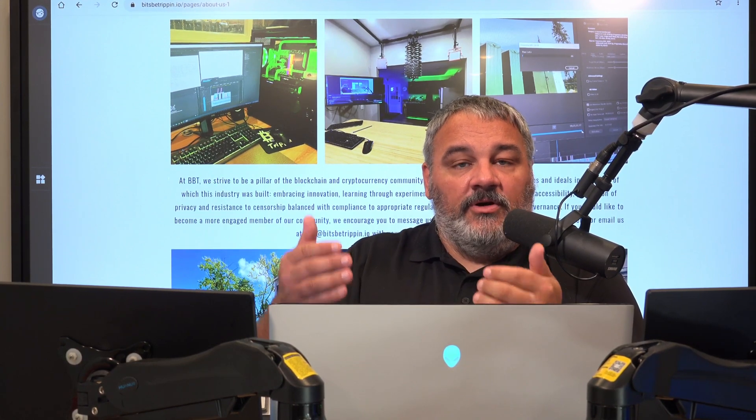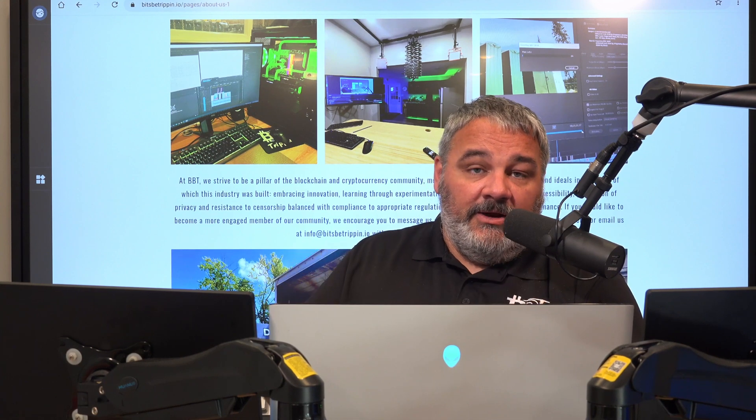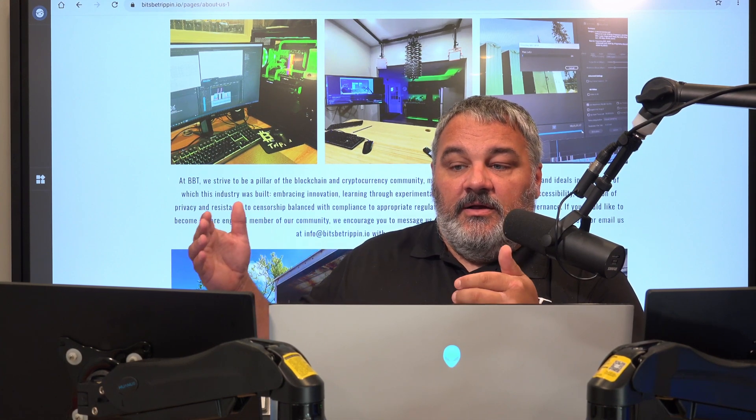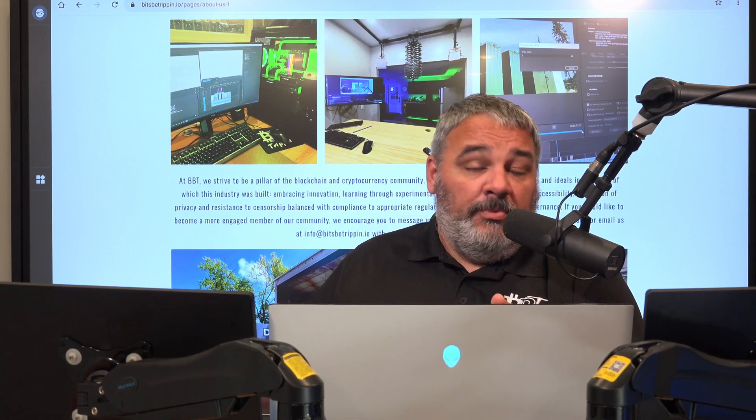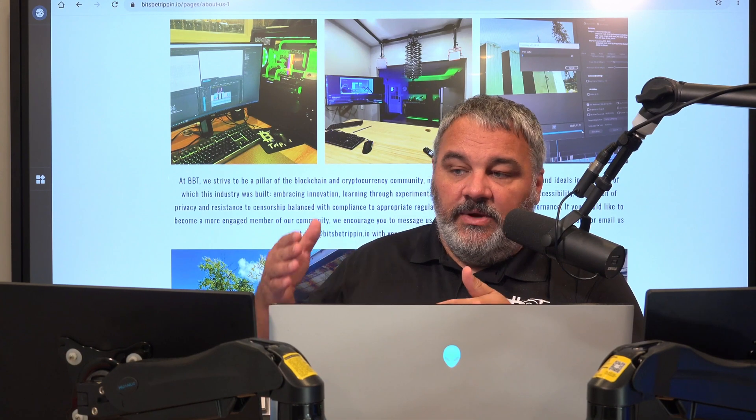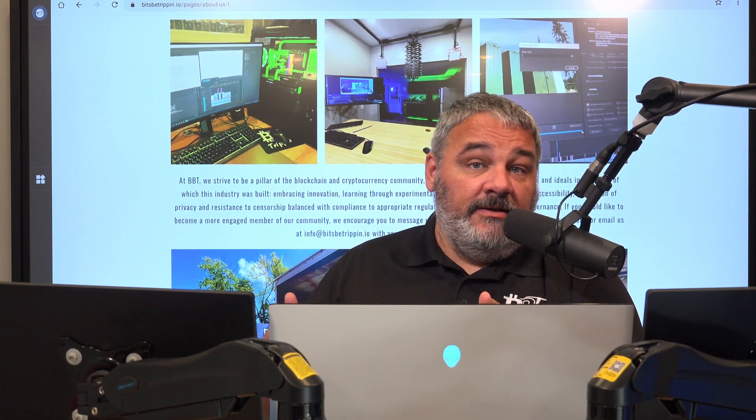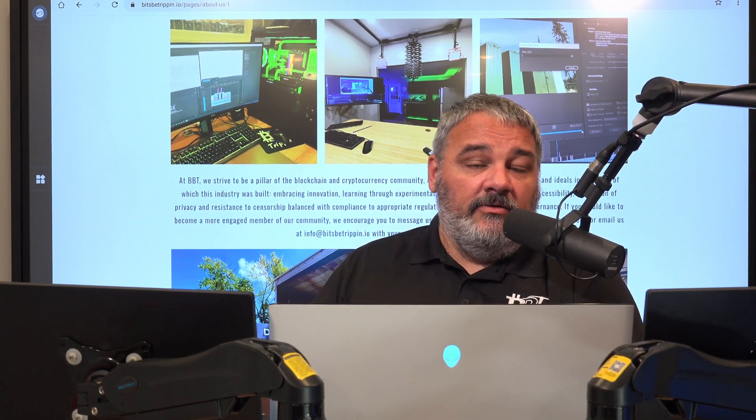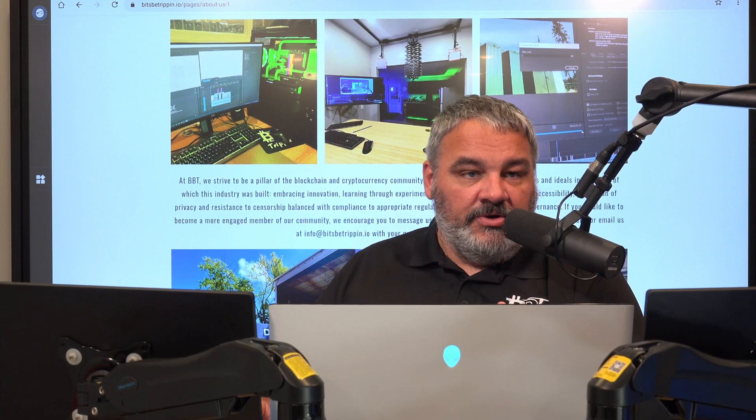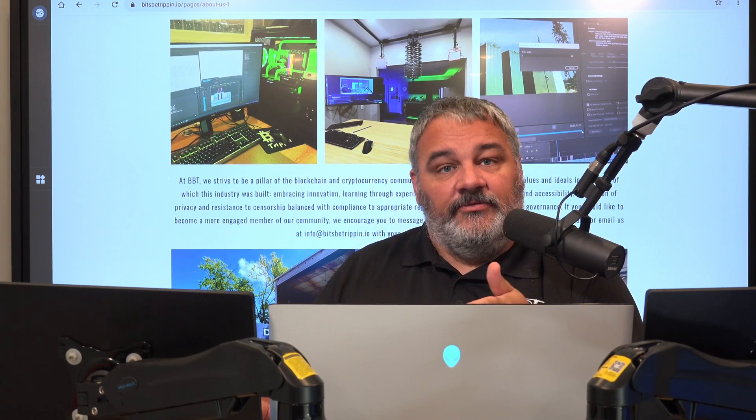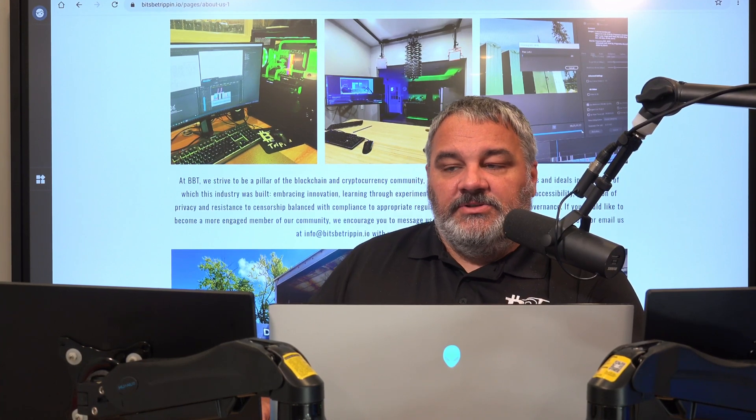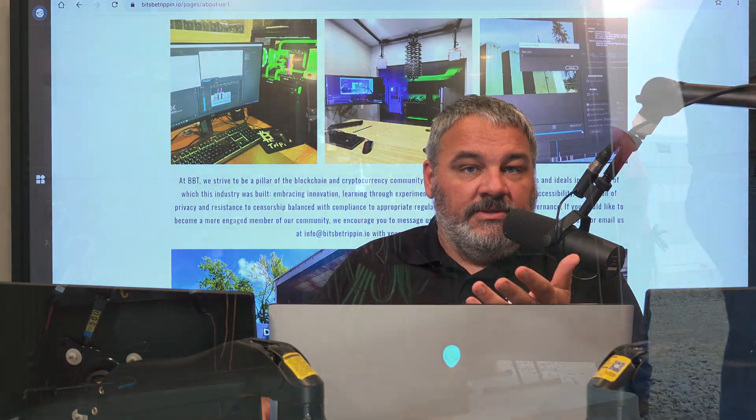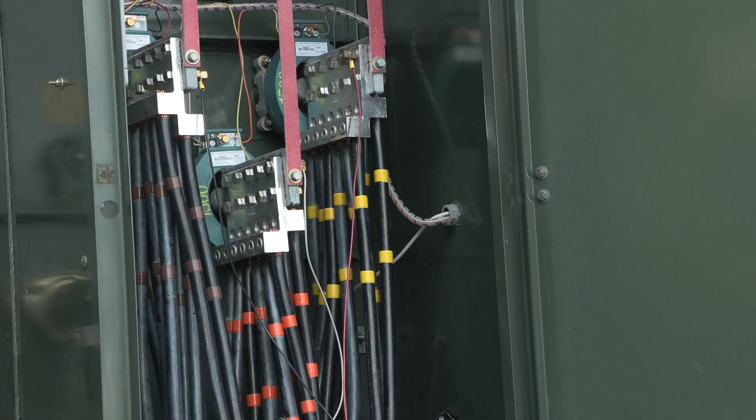The miners that we're using, the Bitmain miners with the firmware upgrade and the Alpha Miner power supplies, support 277 voltages. But we started seeing around 286, 289 voltages. We were getting a little concerned that we were hitting kind of the upper tier of the voltages. So we went out there with the team and did some analysis with the power company.